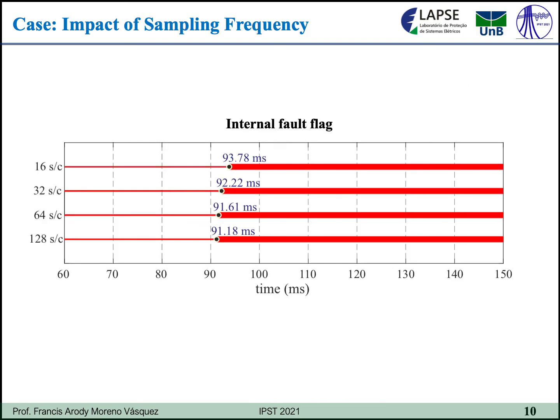Here we assess the impact of the sampling frequency on the operation time of the proposed technique during an internal fault. In that sense, the function was tested for 16, 32, 64, and 128 samples per cycle. It is clear that the operation time is larger as the sampling frequency is lower. Nevertheless, with 16 samples per cycle, we can obtain an operation time lower than a quarter cycle. Also, it must be noticed that the cost-benefit relation is less relevant as the sampling frequency is higher.